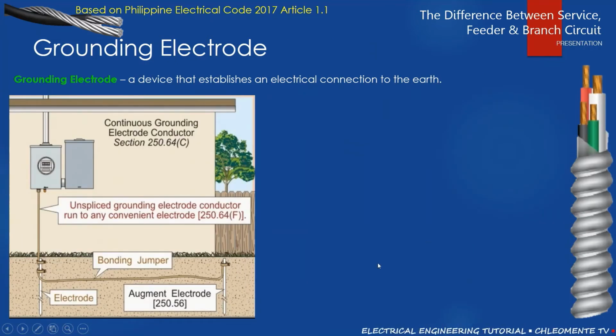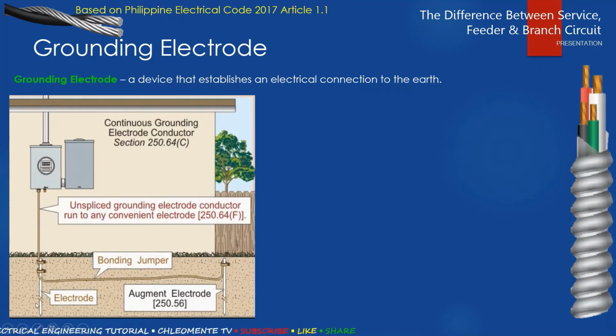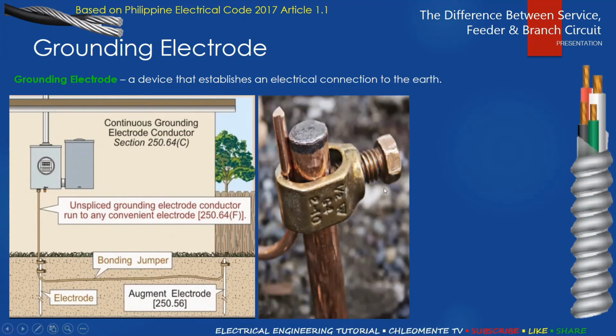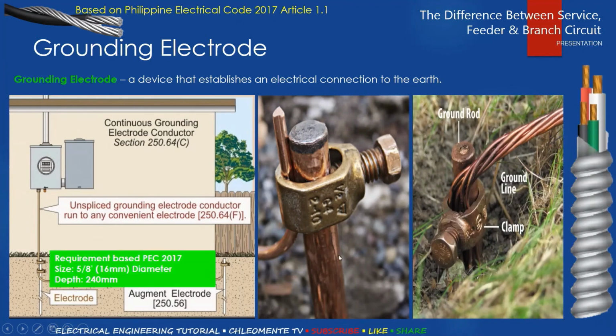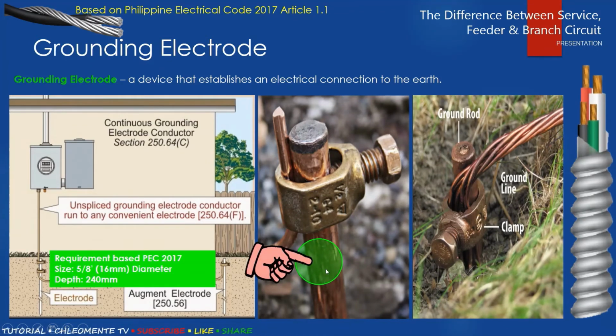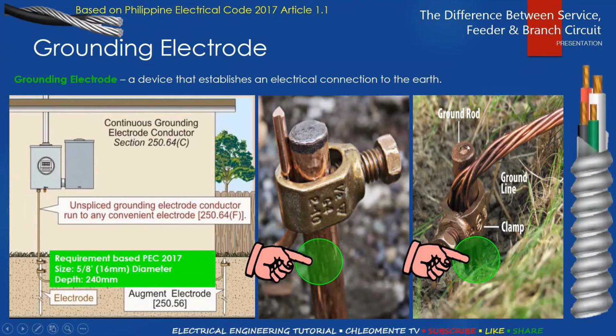Grounding electrode. So, simple, ito yung device na makakonect sa earth. So, grounding electrode. So, ito yan. In this case, ito yung grounding electrode. Bar siya na nakatusok sa earth. In this case, ito yung ground rod. So, may requirement yan si PEC at the size minimum 16 mm diameter at saka babarid mo siya minimum of 240 mm or 0.24 meter.